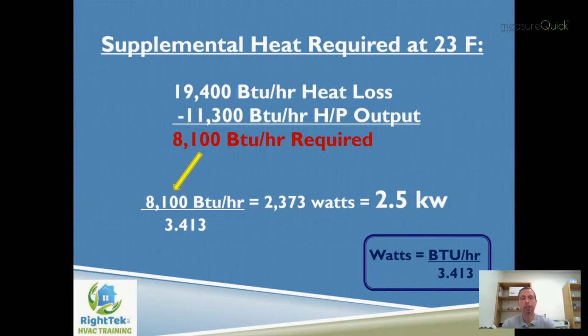So I point this out because a lot of folks go out and they say, oh, I've got a 2 or 3 ton system. Give me a 10 kW heat strip. Well, there's a little bit more science behind it, a little bit more accurate way that we can look at this as a designer to make sure that we're not unnecessarily oversizing the heat strips. Because as all of you well know, when those heat strips come on, the bigger they are, the more amp draw, the more current we're consuming, and the more that watt meter spins and the more it costs people in electricity.